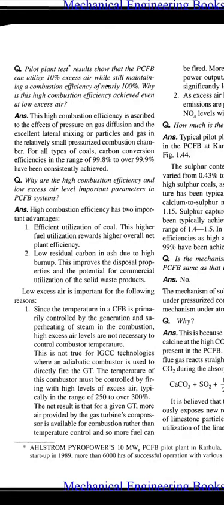Answer: This high combustion efficiency is ascribed to the effects of pressure on gas diffusion and the excellent lateral mixing of particles and gas in the relatively small pressurized combustion chamber. For all types of coals, carbon conversion efficiency in the range of 99.8% to over 99.9% has been consistently achieved.